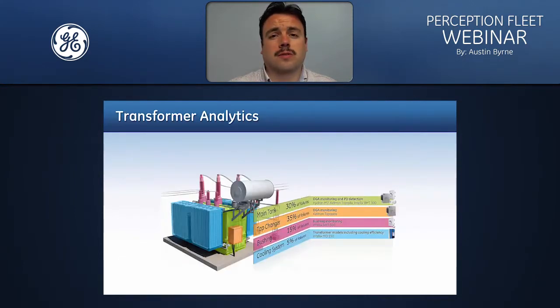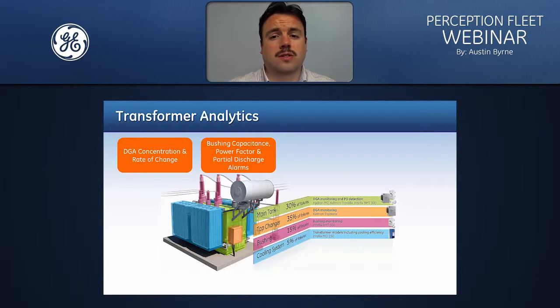Whenever we evaluate transformer information, we look at these specific areas. We look at the main tank, which accounts for 30% of failures, the tap changer, which accounts for 35% of failures, bushing failures, which accounts for 15% of failures in the transformer, and cooling system failures, which accounts for 5% of failures in the transformer. Within Perception, we specifically look at DGA concentrations and rate of change, bushing capacitance, power factor and partial discharge alarms, nameplate data, and transformer criticality information.